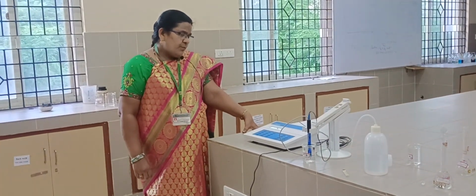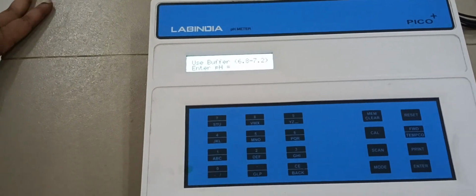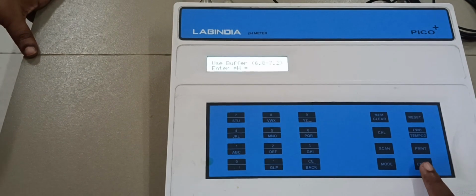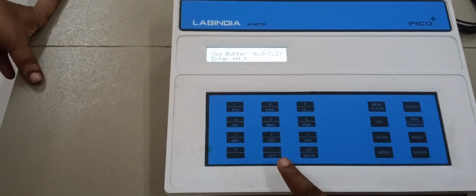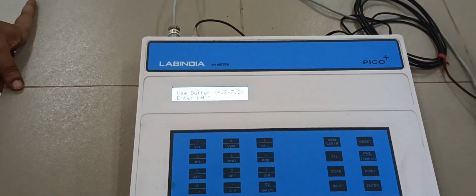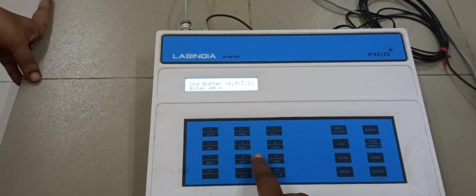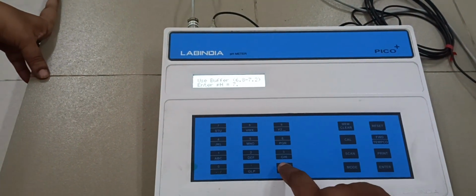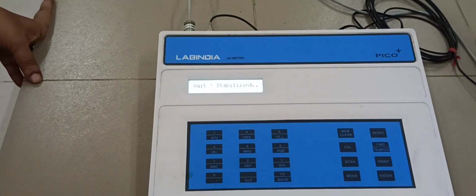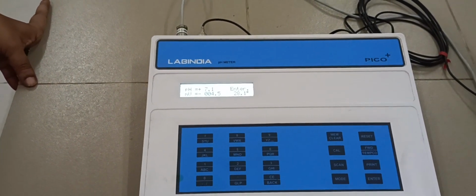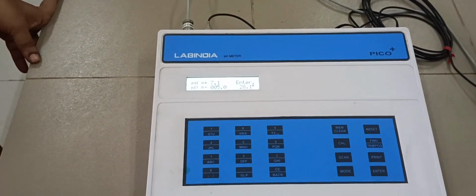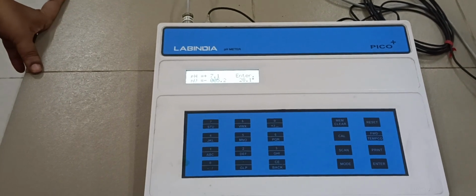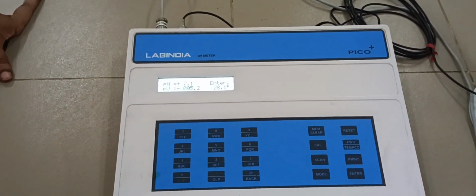Now enter 4.0. After entering 4.0, the instrument was stabilized to 4.0. Then the value is displayed. After buffer 4, keep buffer 7, enter. The same principle applies: exchange of ions causes electric flow, which causes generation of voltage, which gives electrical signals. The display shows the 7 reading.